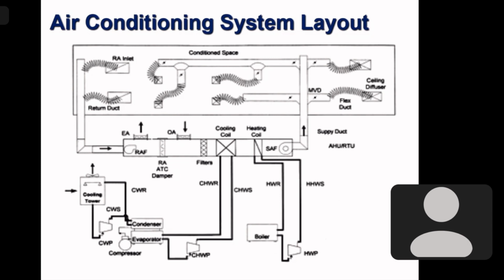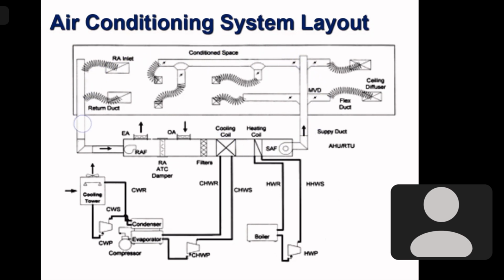You can see on the top there is a room. So we are taking the return air back from the room and we flow it over the cooling coil, recool it and supply it back to the room. And the chilled water gets a little warm. We take it back by the chilled water pump, pass it through the evaporator again, recool it and resend it.